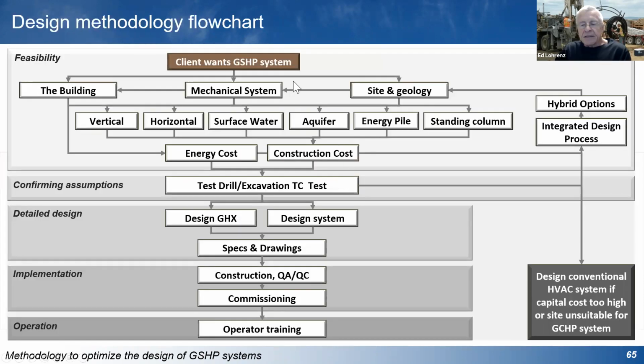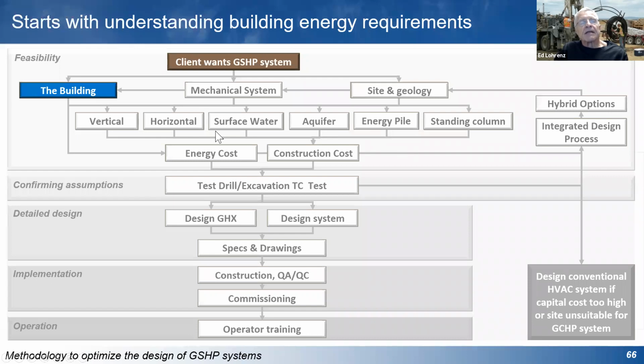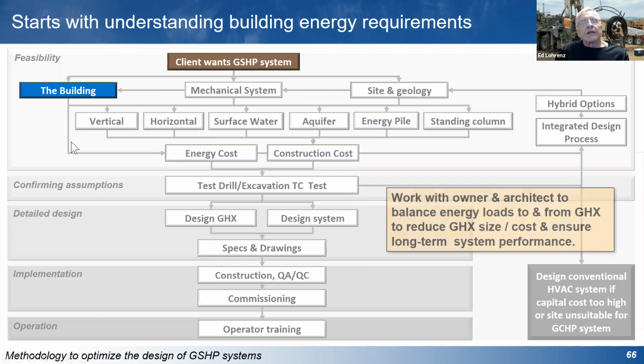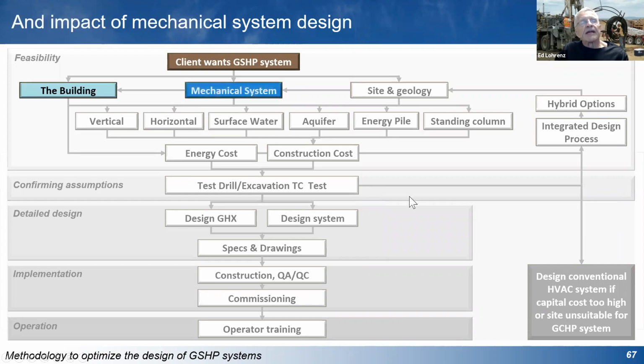So basically, to describe the methodology, if you've got a client that wants a geothermal system, the first thing our approach has been is to really understand how much energy we have to deal with. What is the building design? How much energy does it need for heating? How much energy does it need for cooling? And then we work with the architect to help balance the loads as much as we can from an architectural perspective. Then we do the same thing with the mechanical system, work with whoever is designing the mechanical system itself and go through that same process.